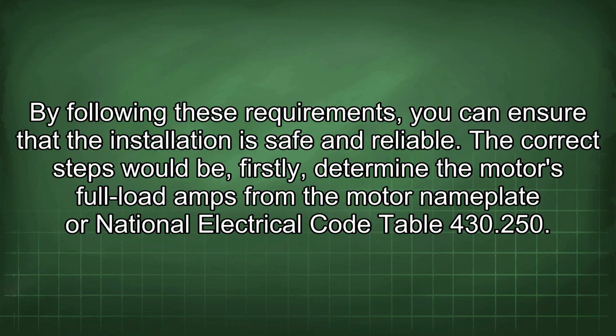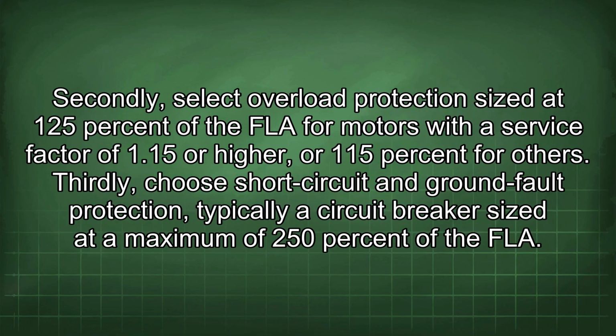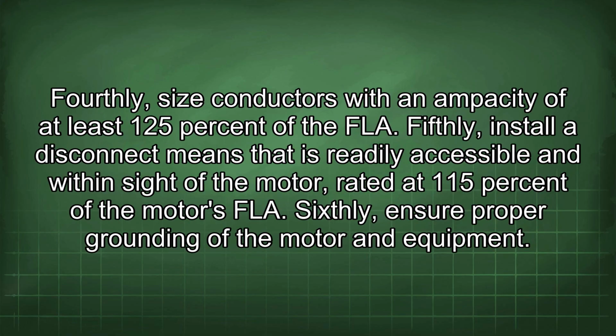The correct steps would be: firstly, determine the motor's full load amps from the motor nameplate or National Electrical Code Table 430.250. Secondly, select overload protection sized at 125% of the FLA for motors with a service factor of 1.15 or higher, or 115% for others. Thirdly, choose short circuit and ground fault protection, typically a circuit breaker sized at a maximum of 250% of the FLA. Fourthly, size conductors with an ampacity of at least 125% of the FLA. Fifthly, install a disconnect means that is readily accessible and within sight of the motor, rated at 115% of the motor's FLA. Sixthly, ensure proper grounding of the motor and equipment.